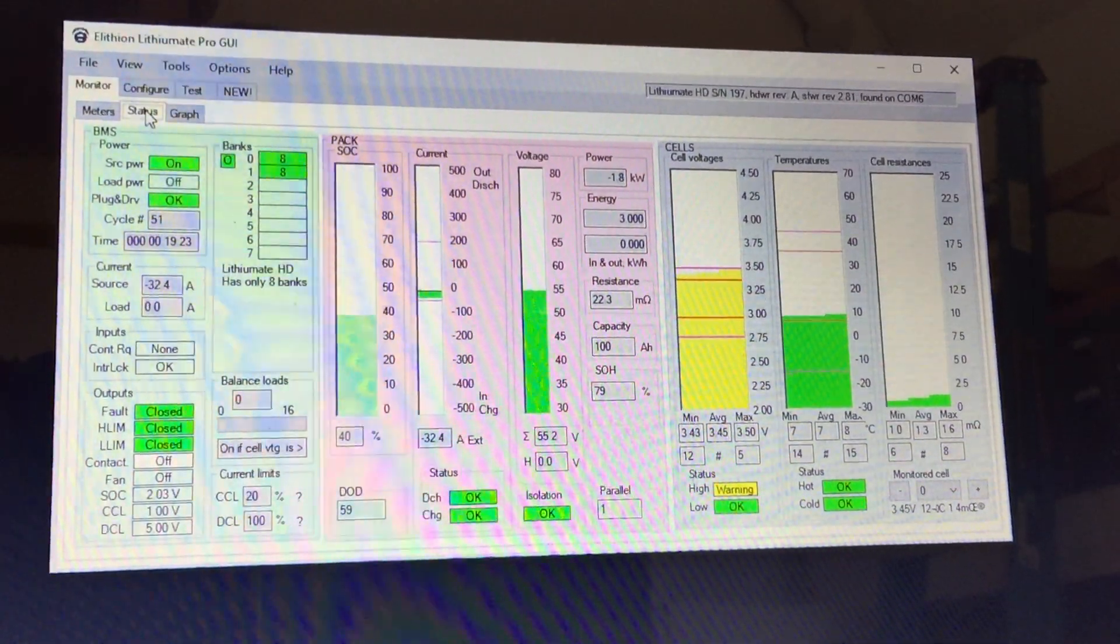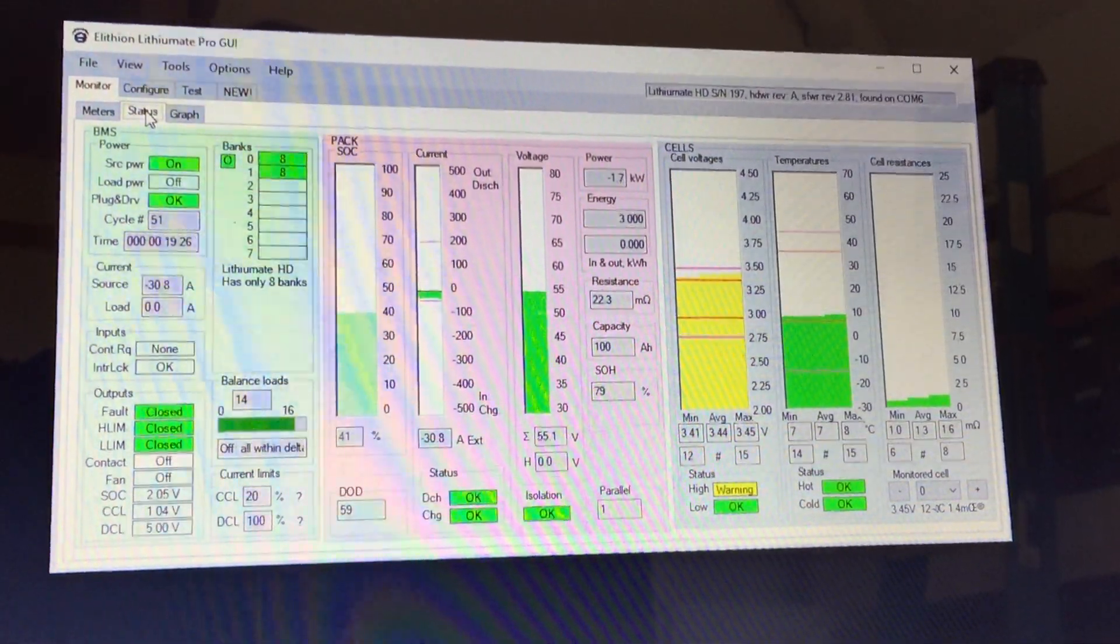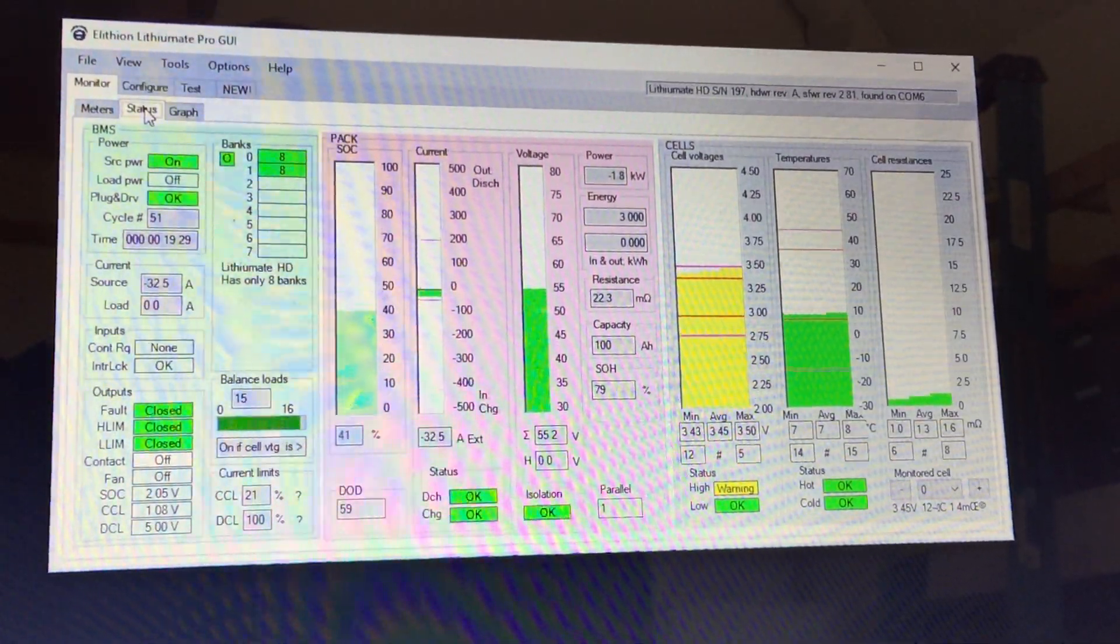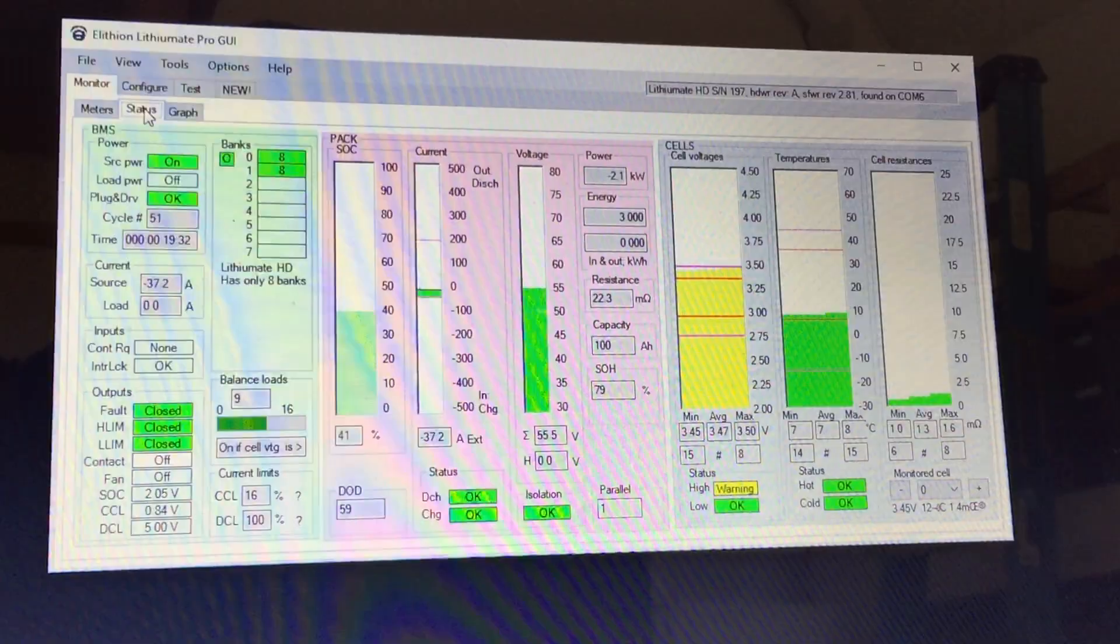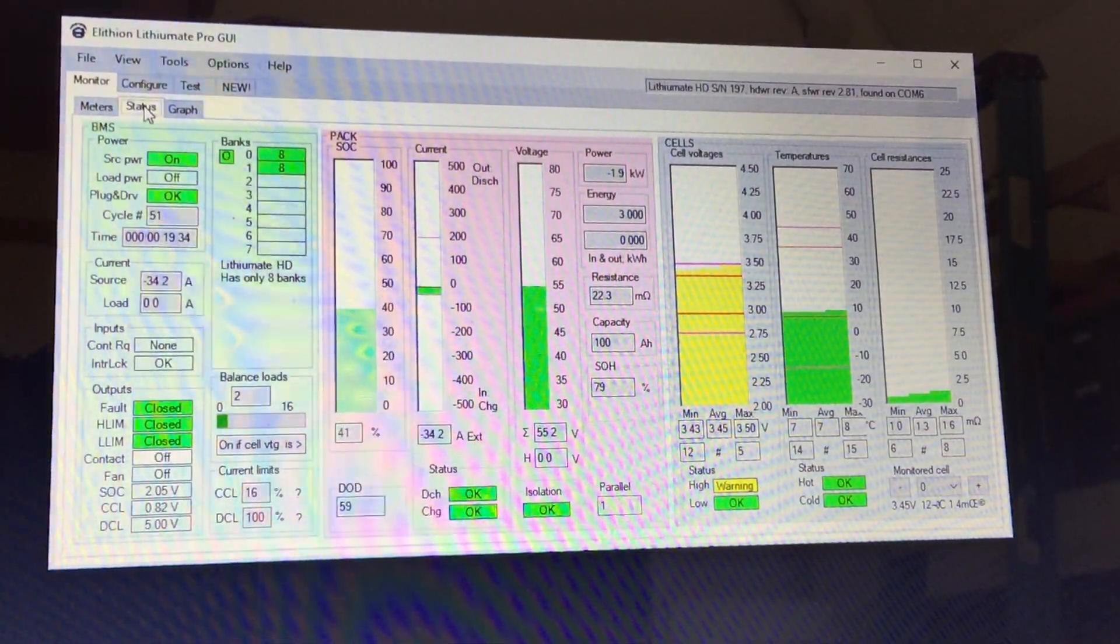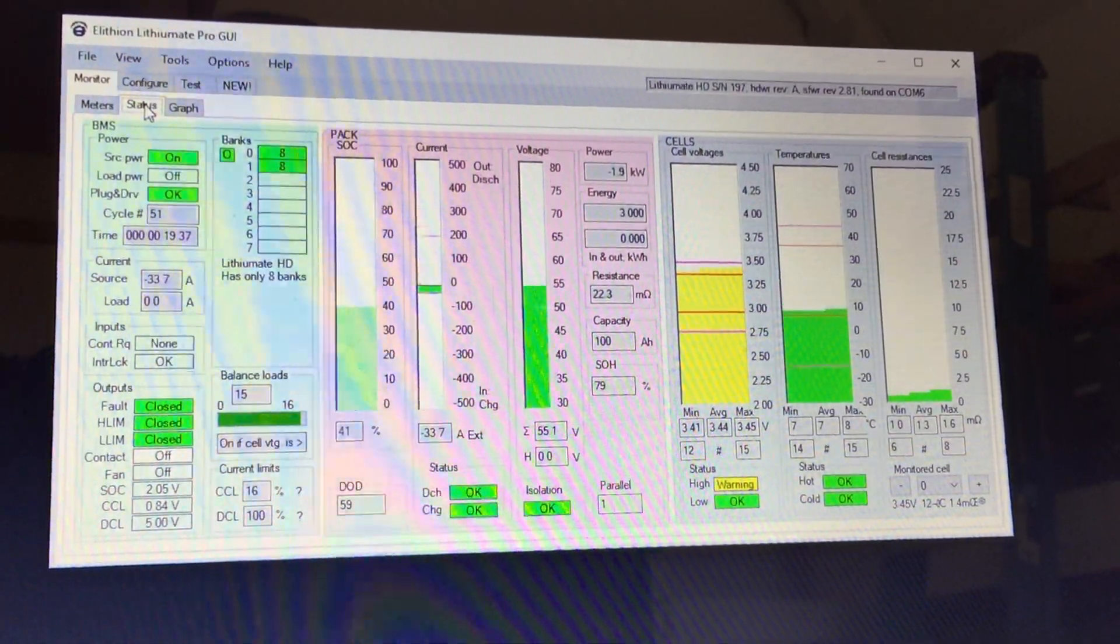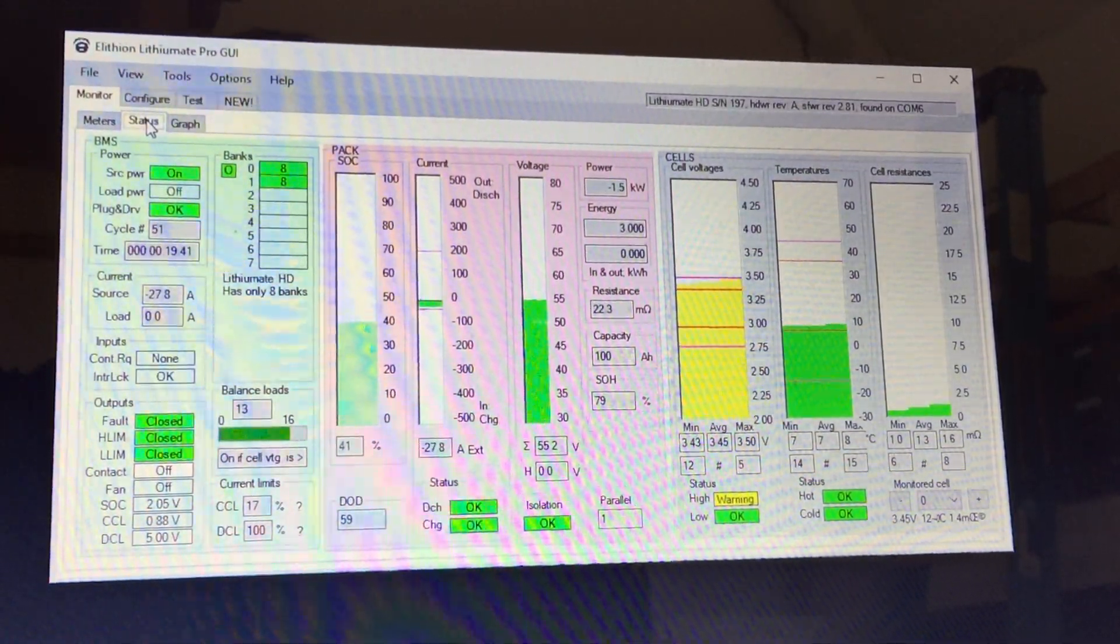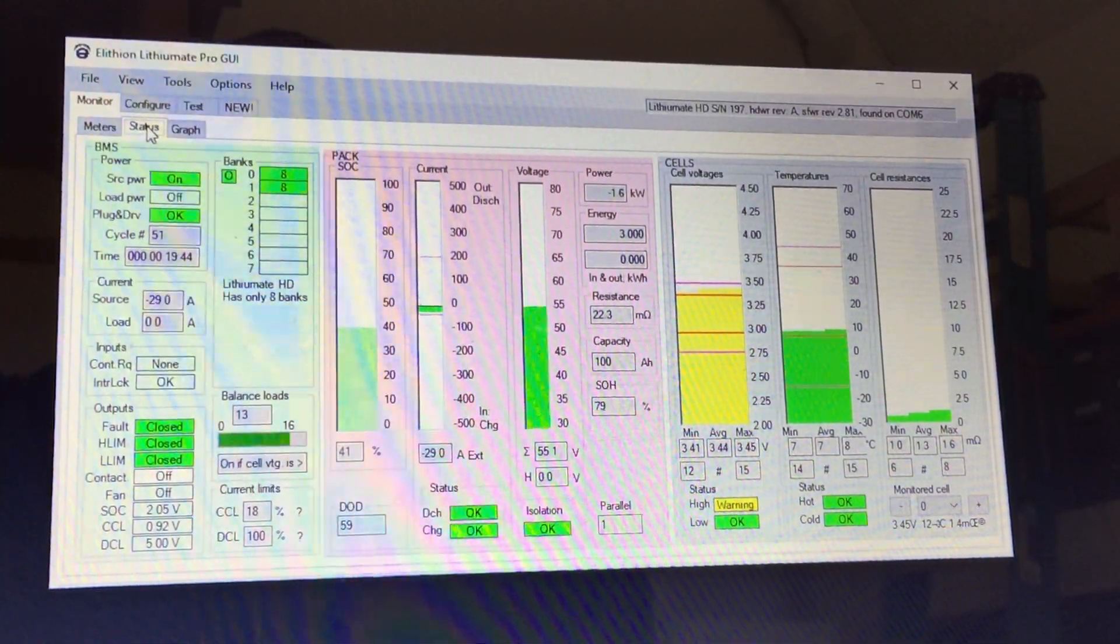What we've been working on is incorporating a slight delay, allowing the BMS some time to push the signals out to the SMA equipment and allow for the SMA Sunny Boys and Sunny Islands to use their frequency shifting capability to slow down the charge rate.